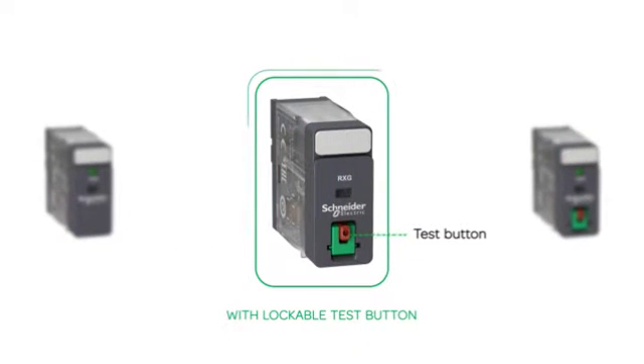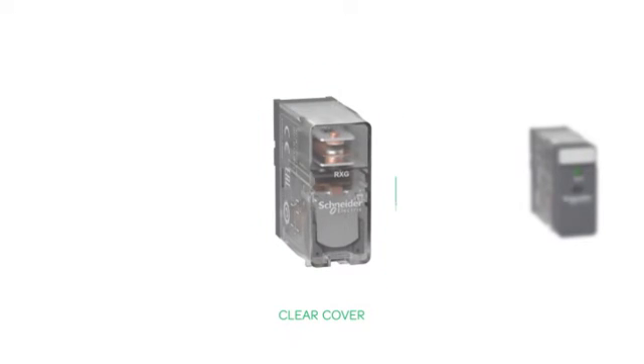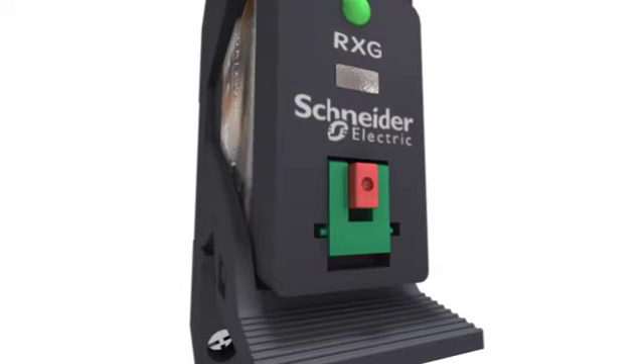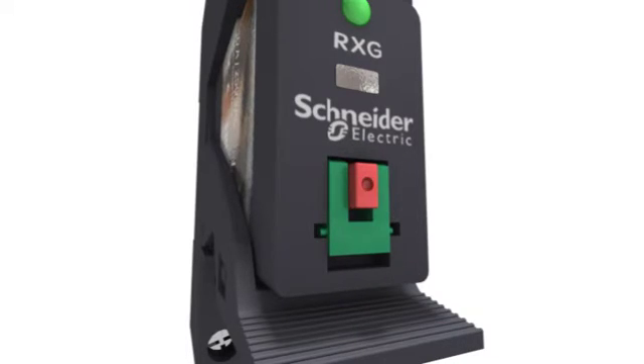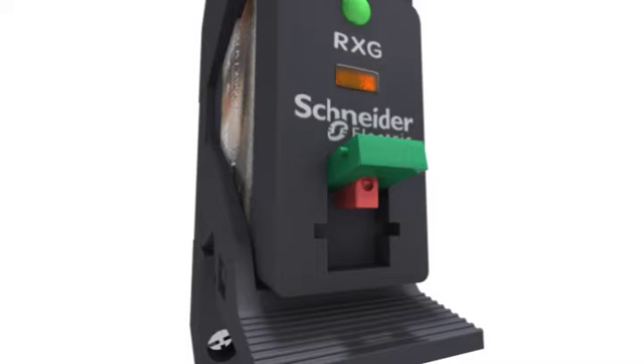Customers can choose full features with lockable test button and LED, or optional features with lockable test button, LED, and clear cover. Zelio RXG is the first relay in the market with a single-step lockable test button. Press the button to enable a momentary switch to test the load circuit without control supply, then flip up the lock-down door to force switch.